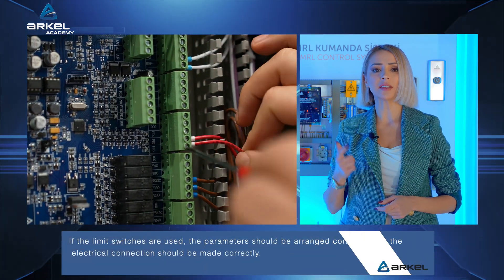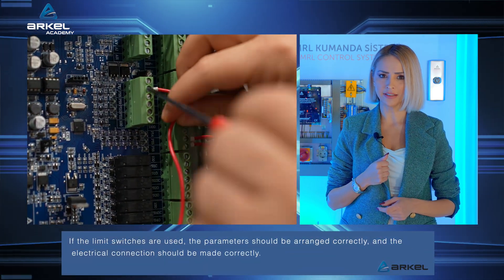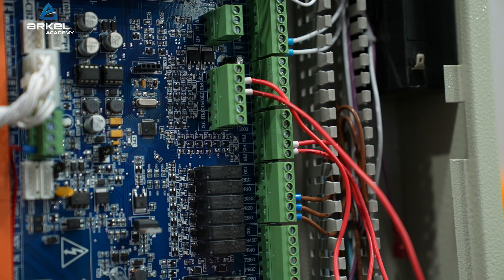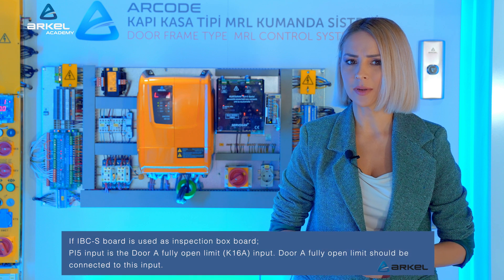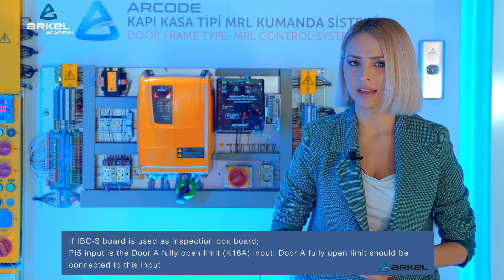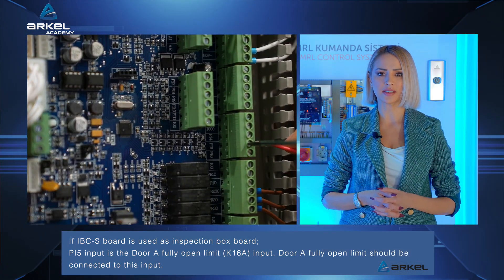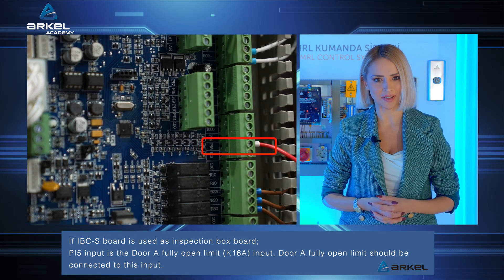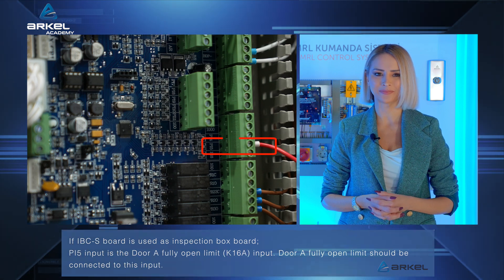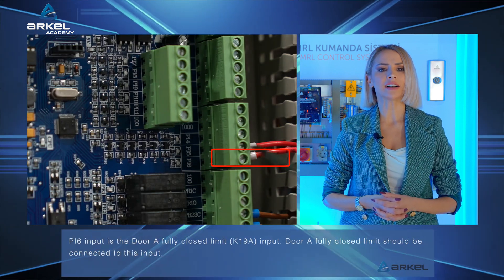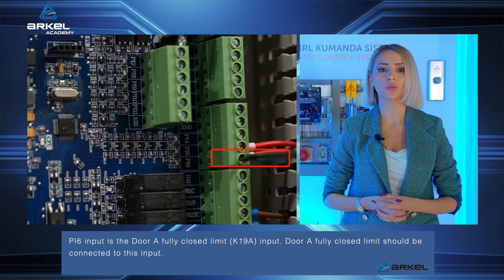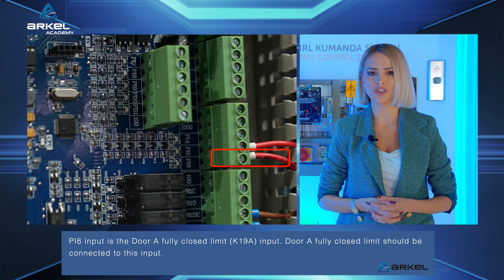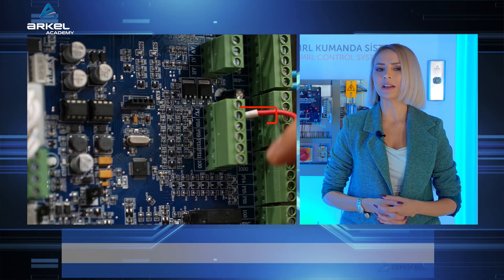If the limit switches are used, the parameters should be arranged correctly and the electrical connection should be made correctly. If the IBCS board is used as inspection box board, PI5 input is the door A fully open limit (K16A input) — door A fully open limit should be connected to this input. PI6 input is the door A fully closed limit (K19A input) — door A fully closed limit should be connected to this input.